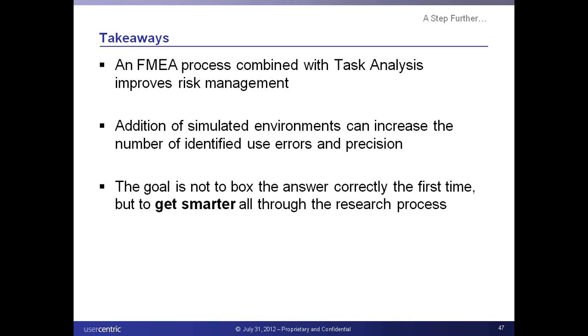The FMEA is very useful because if you uncover things in formative research, hazard risks, add it to the FMEA. Or if you see a use error that is part of the FMEA in a validation study or in formative research, you can then relay it back to the FMEA and start to create risk mitigation controls, as well as understand that sometimes use errors happen, but the harm was negligible and the likelihood was low. So you actually use the FMEA to essentially assess the risk found in subsequent research inside validation or formative studies.